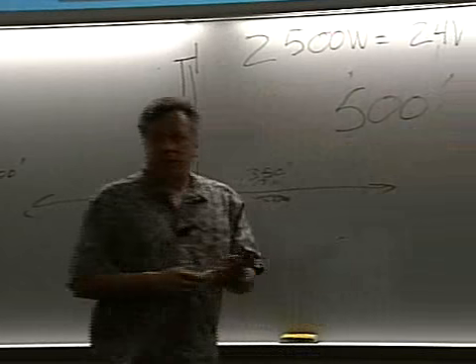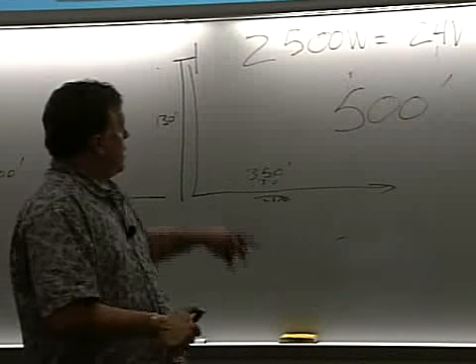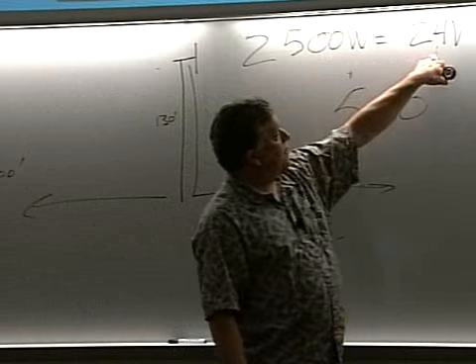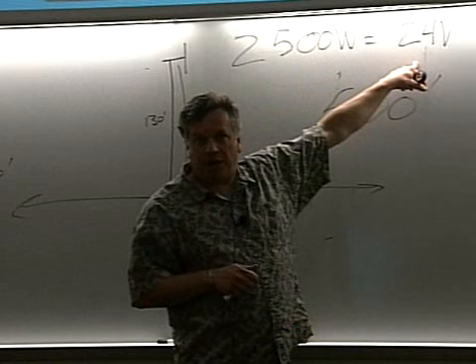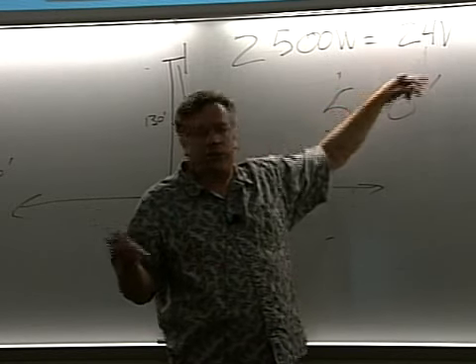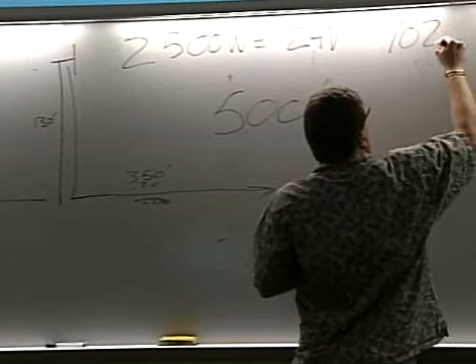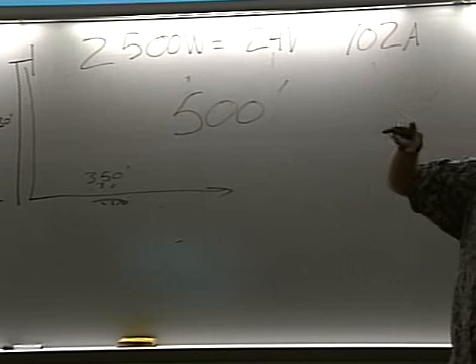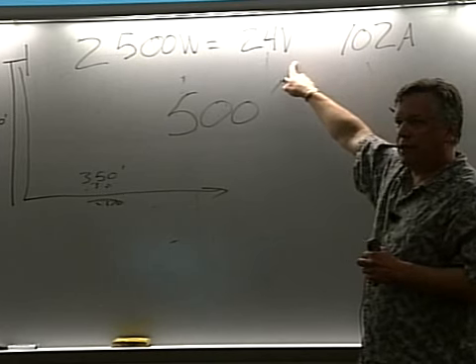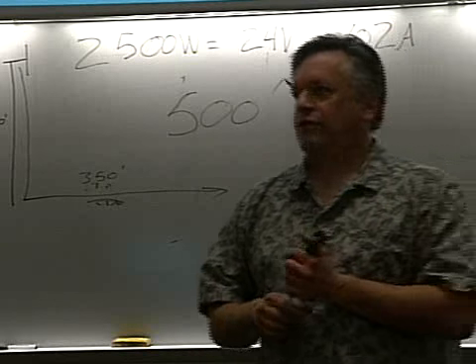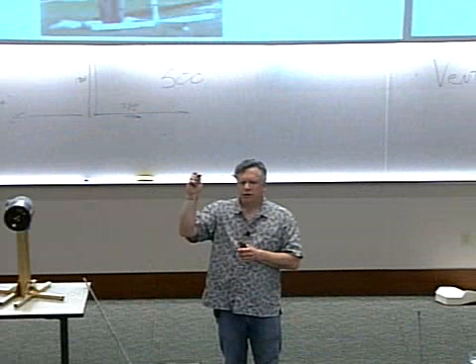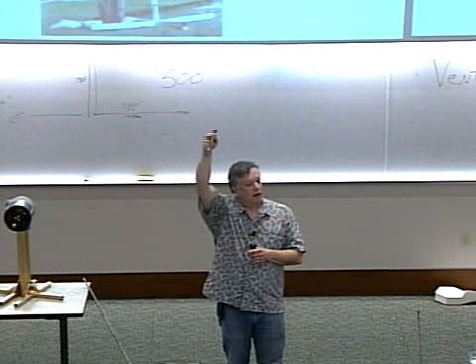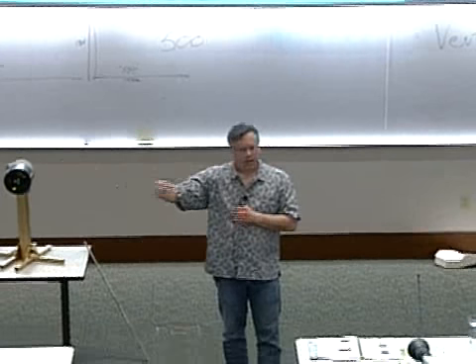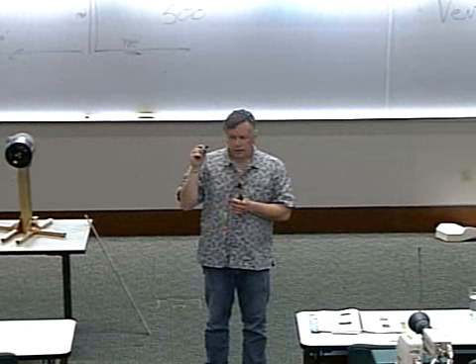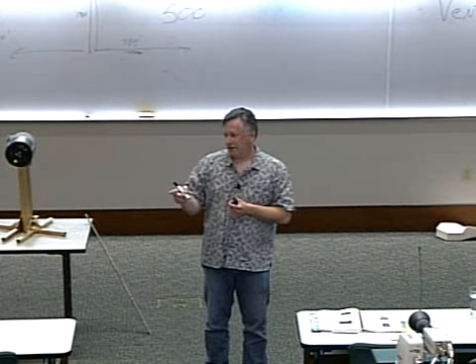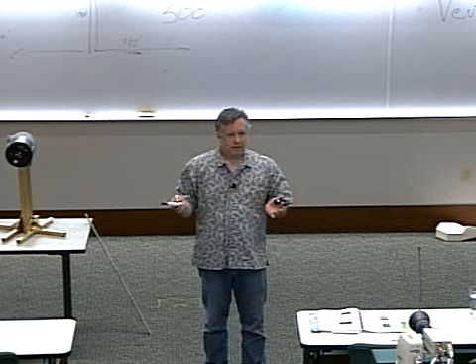All right, who's an electrician? Volts times amps equals watts. How many amps is this unit running at? About 100 amps, 102 or so. All right, 102 amps. If we want 2 to 5% wire loss, 500 feet running at 24 volts, what kind of conductor size do we need? Gargantuan, a huge diameter. We're going to have a huge conductor about this size running from the tower top all the way down and over to the balance of systems. Can we do it? Absolutely. We're going to size the conductor to have a minimum of 2 to 5% wire loss, and it's going to cost. How far can you take that? How big is your checkbook?